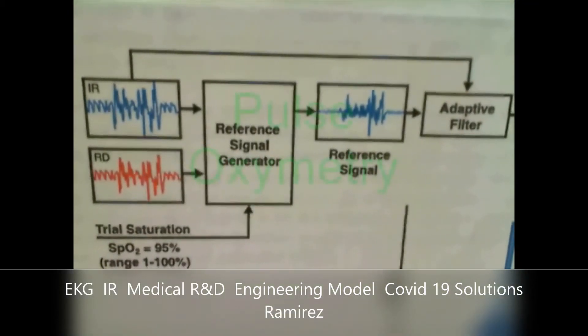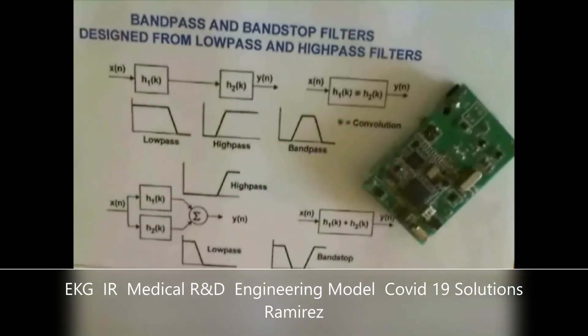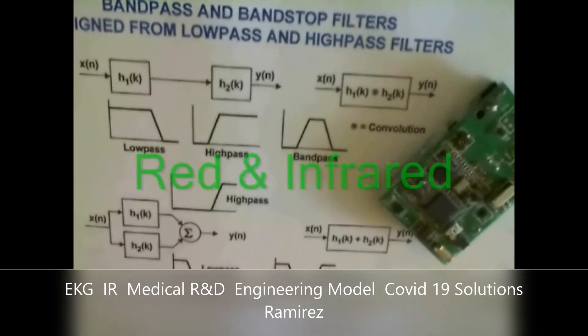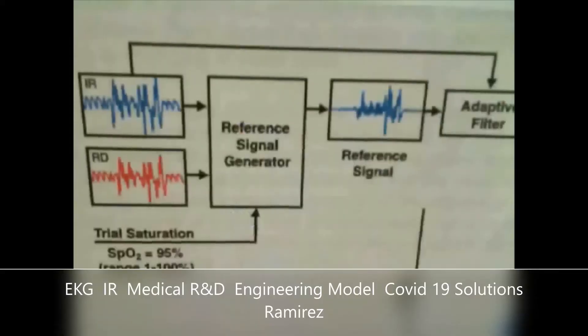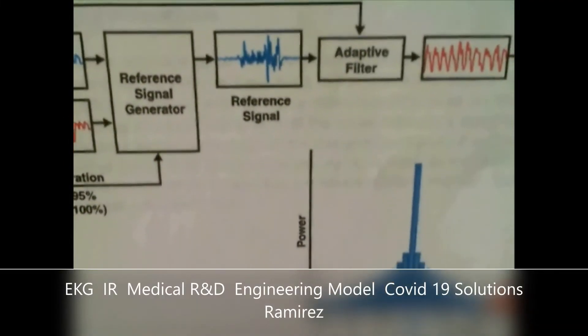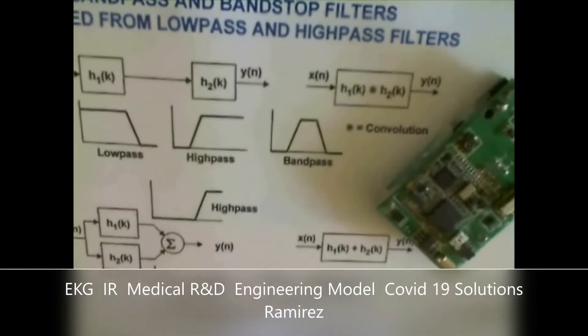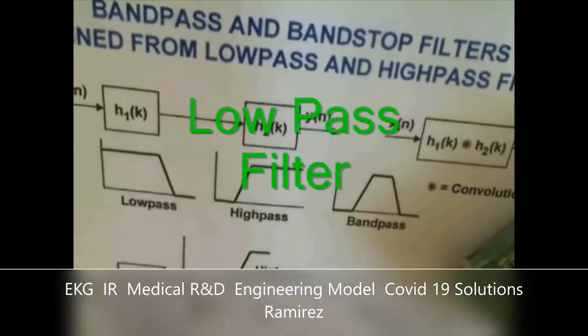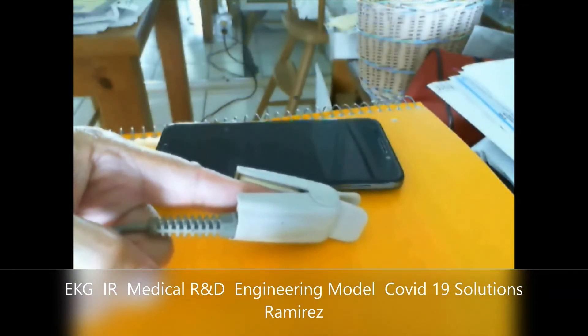The technique of pulse oximetry is based on two principles. First, the color of blood, which depends on oxygen saturation, is determined using two wavelengths — red and infrared spectrophotometry. Second, the amount of arterial blood in tissue due to changes during pulsation. To determine the arterial oxygen saturation, the pulsation of arterial blood flow is used. Body motion feeds into a second-order high-pass filter to pass pure AC signals without DC components, and a low-pass filter increases the amplitude of the heartbeat signal and compresses high-frequency noise from the system as well as disturbance from the environment.